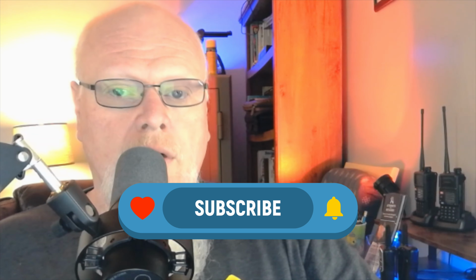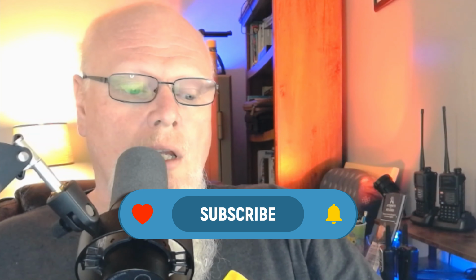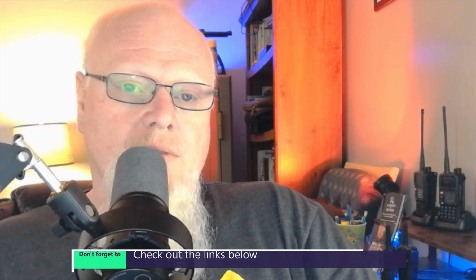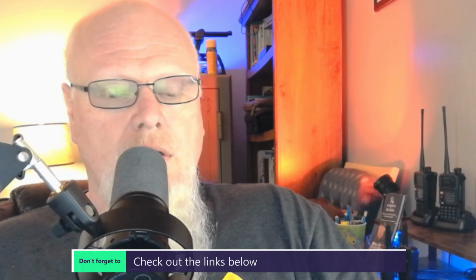Basically what it is, just me doing some troubleshooting a while back. I'm finally just now getting around to editing the video. And basically what we're doing is trying to troubleshoot where we have some devices that have gone offline, and the Bus Health Index is a useful tool within Metasys that will let you know if you're headed in the right direction trying to find a device that's offline.